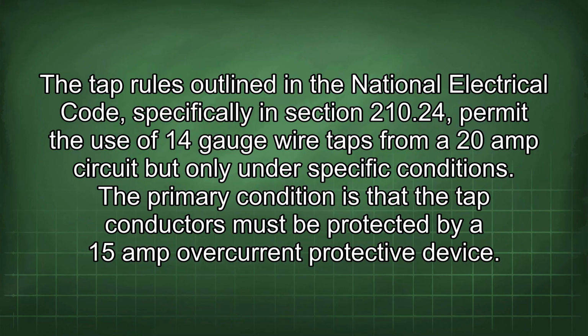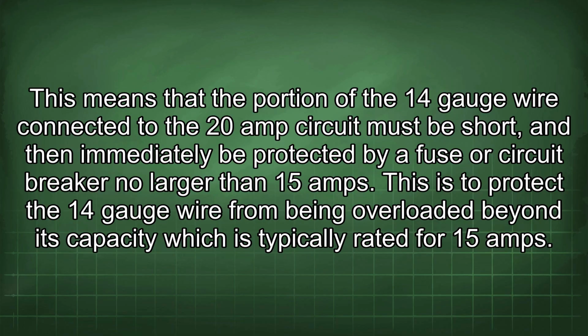The tap rules outlined in the National Electrical Code, specifically in Section 210.24, permit the use of 14-gauge wire taps from a 20-amp circuit, but only under specific conditions. The primary condition is that the tap conductors must be protected by a 15-amp overcurrent protective device. This means that the portion of the 14-gauge wire connected to the 20-amp circuit must be short, and then immediately be protected by a fuse or circuit breaker no larger than 15 amps.